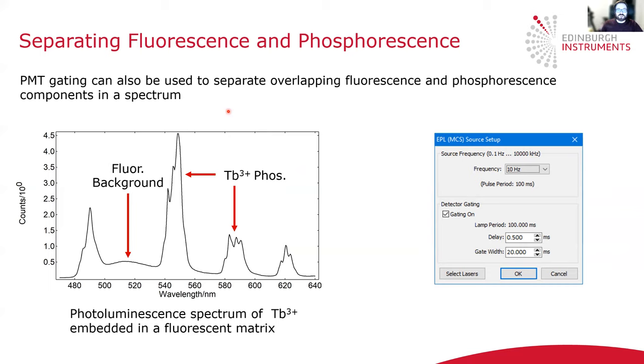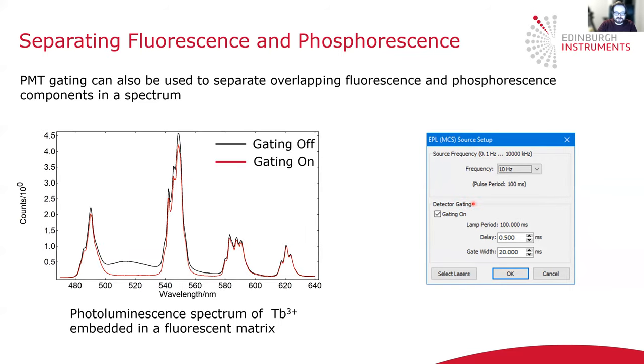The other advantage of having a gated PMT is that it allows you to separate fluorescence and phosphorescence components in the spectra. Using the same terbium and fluorescence sample, when we look at its emission spectrum with no gating we have the transitions from the terbium but also a broad fluorescence background from the matrix. By using detector gating, the spectrum can be acquired only during the emission of the phosphorescence component, so the fluorescence background is removed and you get the spectrum of just the terbium component. Gating can therefore be used to separate the phosphorescence from the fluorescence spectrally.